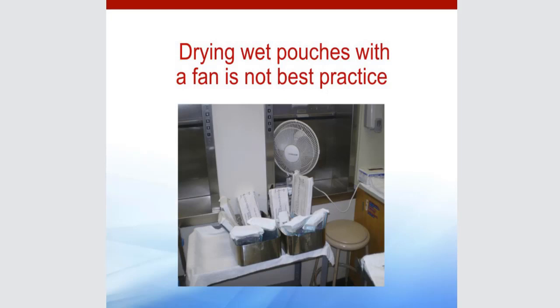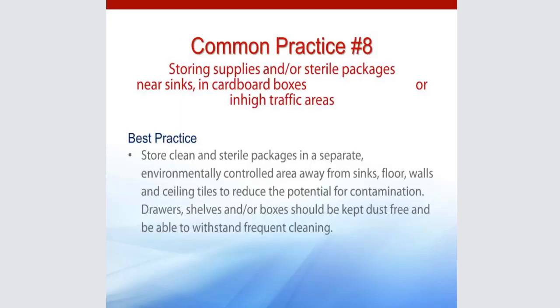This is obviously considered an off-label use. You cannot use a fan to dry the pouches. That's not an appropriate method of getting them to dry more quickly. The other thing you want to make sure, besides loading appropriately and not overloading, is that you are not putting wet instruments into your pouch or wet instruments into your cassettes and then wrapping them. Because if you put 7 instrument pouches in your sterilizer that still have wet instruments, or if you run your cycle so tight back to back that the tray itself in your sterilizer is still wet, you've actually increased the volume of water in the sterilizer, and your dryer is calibrated to a specific volume of water, and if you've added more water in, that could be causing part of the problem with the wet packs.